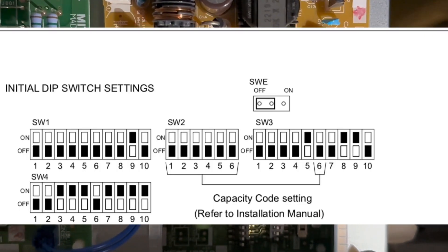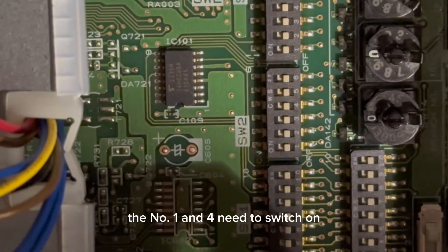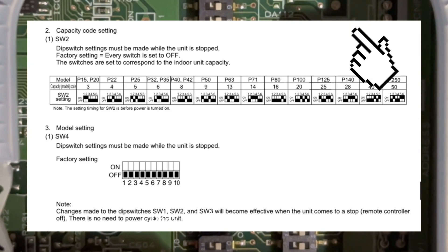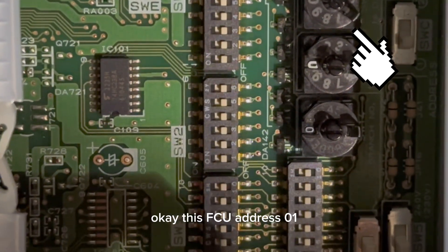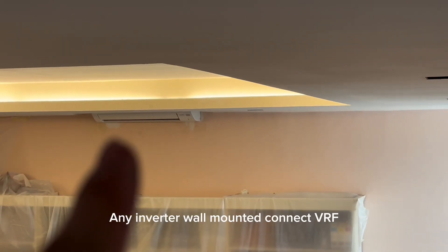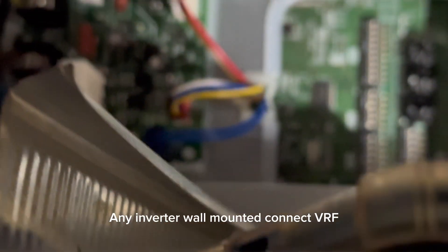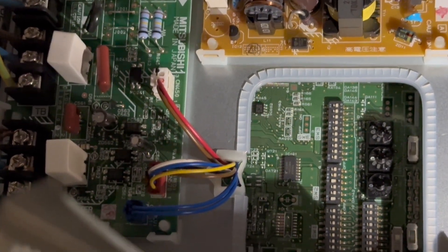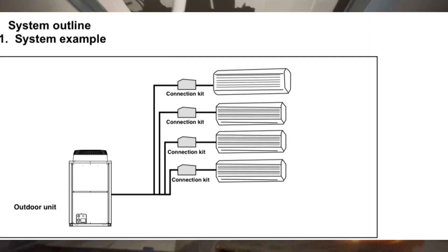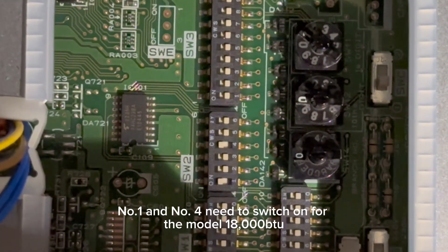For the SW2 switch — it's not yet set. Number 1 and 4 need to be ON for the model 18,000 wall mounted. This is FCU 01. Any wall mounted connected to VRF needs to connect to this box. Number 1 and number 4 need to switch on for the 18,000 BTU wall mounted model.